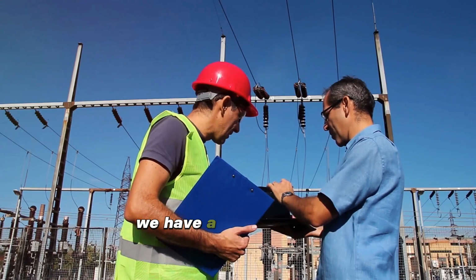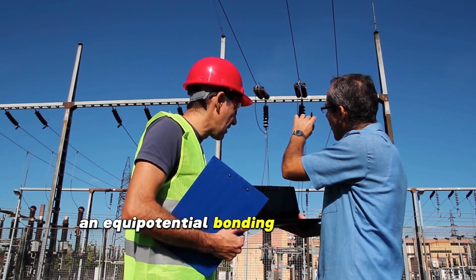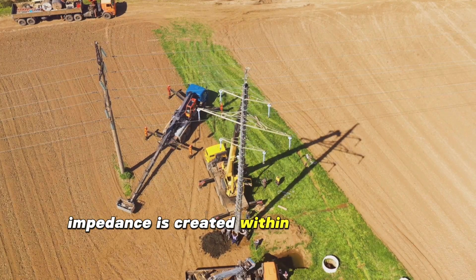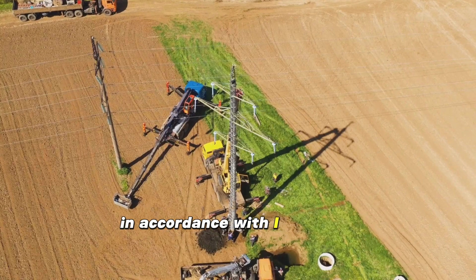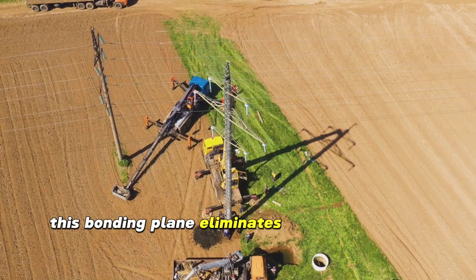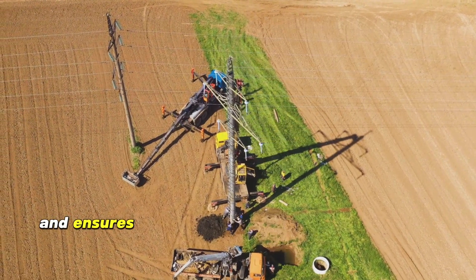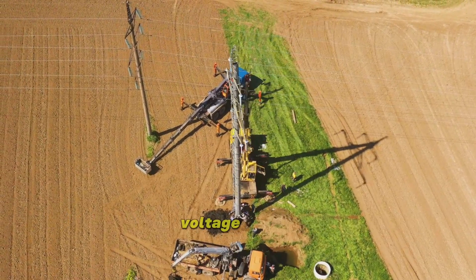But don't worry, we have a solution to this. An equipotential bonding plane with low impedance is created within the substation in accordance with IEEE 80. This bonding plane eliminates voltage gradients and ensures that any fault is cleared within 3 voltage cycles.